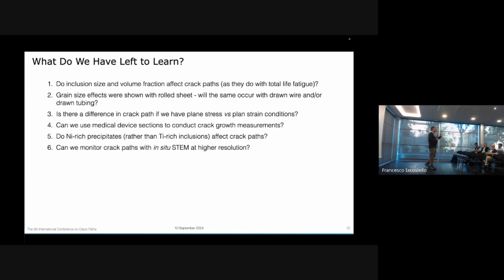So we do use safe life design, and I spend a lot of time interacting with the FDA. And the FDA told me many, many years ago, he said, Alan, there are 3 things that I want you to figure out: fatigue, fatigue, fatigue. Okay? And that's what I devoted my career to, looking at fatigue as I know it. So, thank you for your insights. You're absolutely right. It's the best model we have now. We want to do something better.